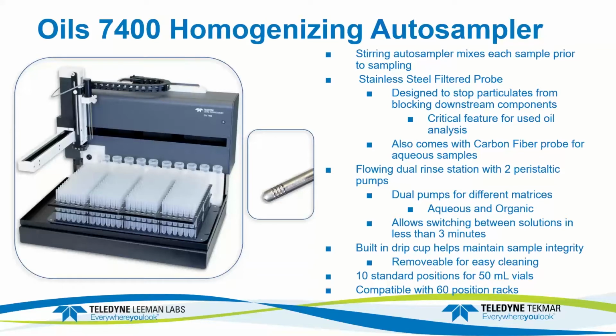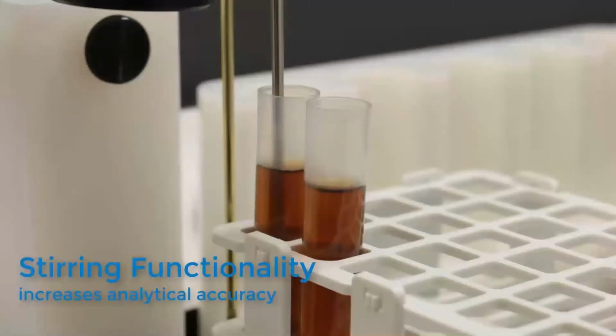And the other advantage of this auto sampler is it has a dual rinse station and two separate peristaltic pumps, one to run organics, say with kerosene as the solvent, and one to run coolants in aqueous mode. Rather than having to change out all the tubing, you can simply move the rinse station and the auto sampler automatically detects the location and turns on the appropriate peristaltic pump. Has a drip cup, prevents samples from contaminating each other. And in this case, it's set up with 10 standard positions with 50 ml vials and 60 position racks. So we'll take a look at the auto sampler in operation.